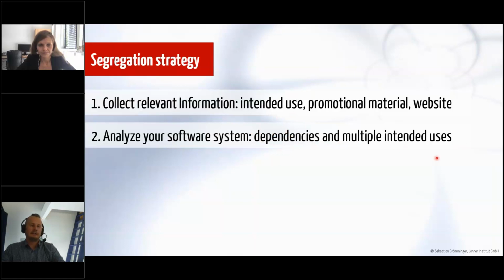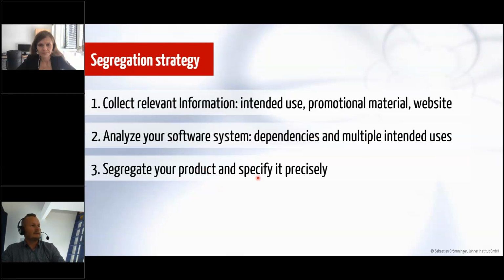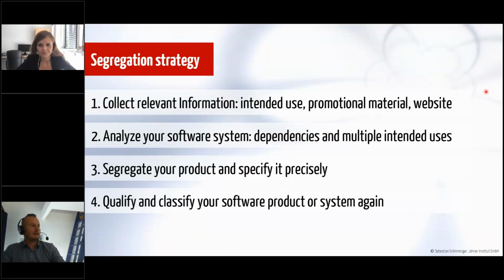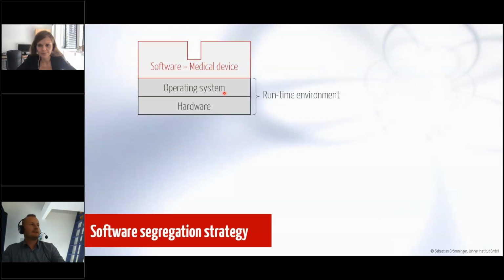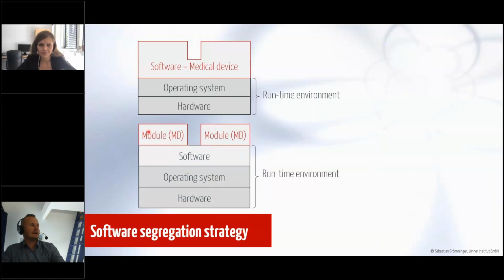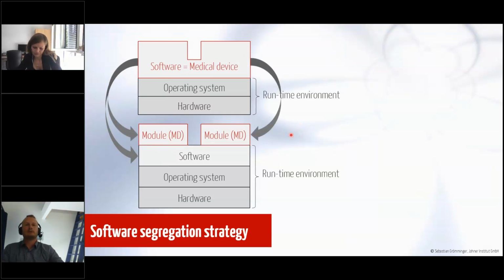If there are dependencies and multiple intended uses, there is certainly a chance to get into lower classes, at least for parts of the software system. Then segregate your product and specify it precisely with the intended use for each part of the software, and then qualify and classify your software product or products and systems again. How can we do that? For instance, you have the software system running on a hardware and an operating system, which is called the runtime environment, and your software is in general a medical device with several intended uses, which is indicated with these two parts here. After segregation, you may have a generic software system and modules that you install onto the software system, and then the runtime environment changes, and you have split your software into a generic software part and a medical device module, and maybe a second or a third or even more modules. This allows you to classify each module individually.